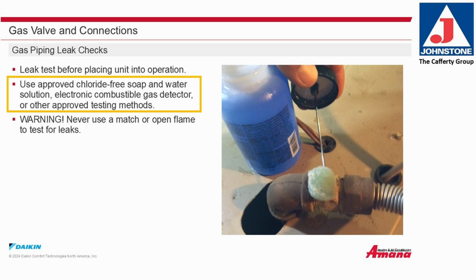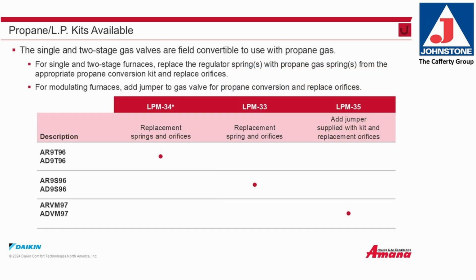Use approved chloride-free soap and water solution, electronic combustible gas detector, or other approved testing methods. Never use a match or open flames to test for leaks. LP kits available. The single and 2-stage gas valves are field convertible to use with propane gas. For single and 2-stage furnaces, replace the regulator spring or springs with propane gas springs from the appropriate propane conversion kit and replace the orifices. For modulating furnaces, add a jumper to the gas valve for propane conversion and replace orifices.